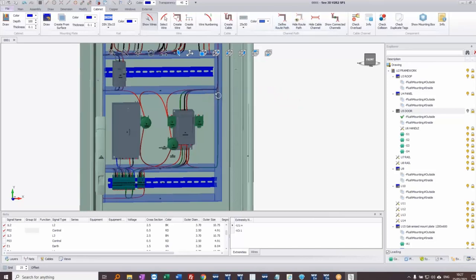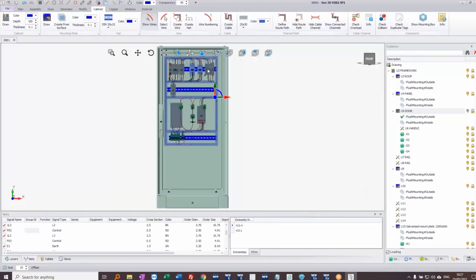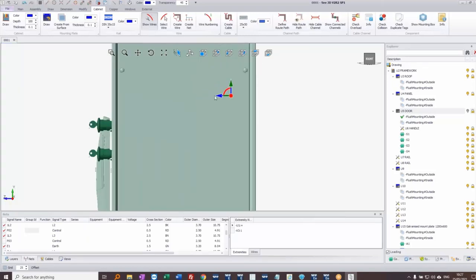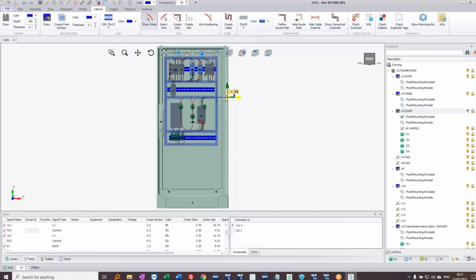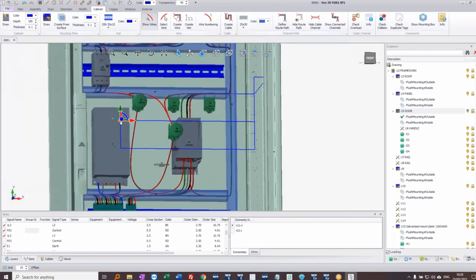I'll use 'Define route path' to route cables around the side. I click to choose a departure point from the cableway, tap T for midpoint, and set the starting position. I drag it to the side, then switch to a right-hand view to route along the side of the panel. Back to a front view to route across and down. I right-click at that point and then add another route path section, snapping to the correct point using object snaps.